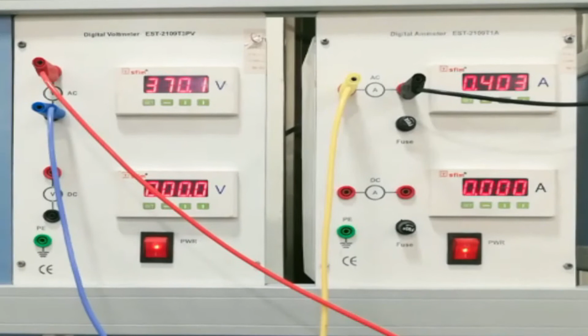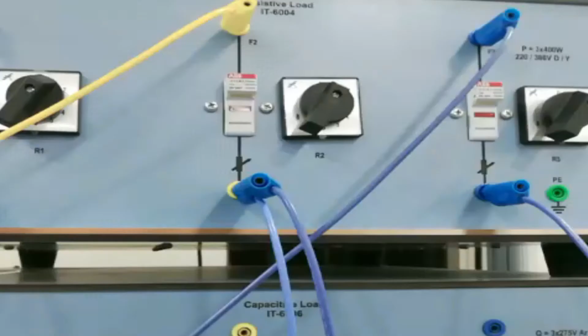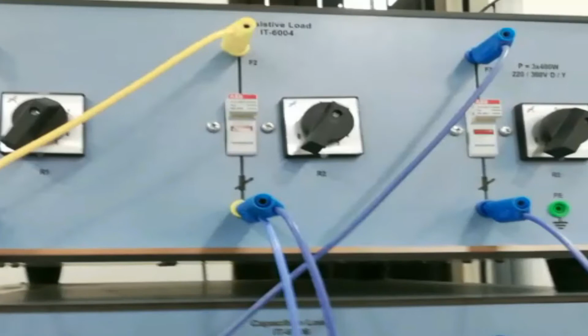Now let's measure the voltages and currents. You can see here the sending end voltage is 370.1 and the sending end current is 0.403. These are the receiving end voltages and currents. The receiving end current is 0.23 and the voltage is 396. Real power is 56 watts and the reactive power is 66.